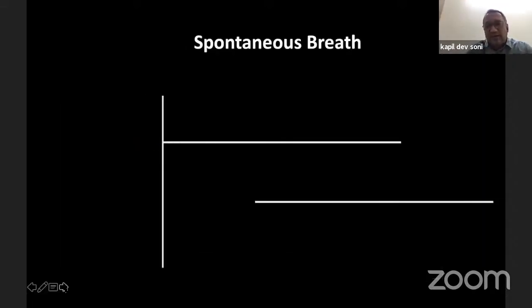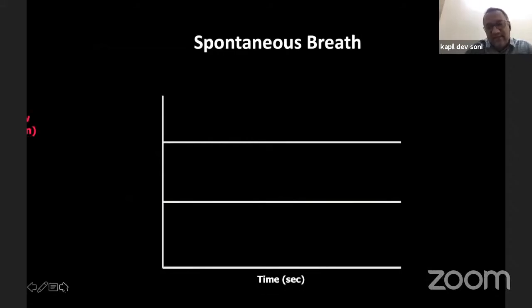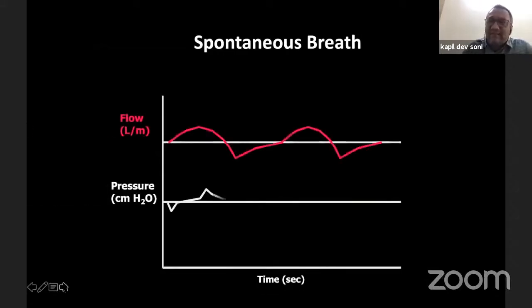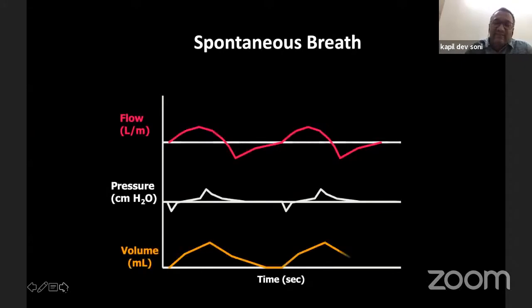So this is how the graphics change. These are called time scalars. There are 2 things: one is time scalars, the other is loops. These are graphics displayed on the ventilators, and they provide a lot of information to clinicians who are trying to synchronize the patient's effort with the machine. So what you need to look at is the flow, pressure, and volume. Volume would always be on the positive axis, whereas the pressure can go towards the negative axis as well. The flow can vary from the positive to the negative axis.